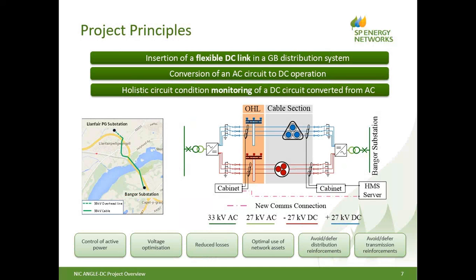So we talk about the project principles. The left-hand side diagram shows you the existing cable circuit. It's interesting in as much as it's got a small section of overhead line. It's only 5 spans, and it runs for about 500 metres at the far end near the Llanfair PG substation. So that will give us an opportunity to see how DC operates on overhead line circuits, the effect on insulators, and whether there are any detrimental effects or things that we need to worry about there.